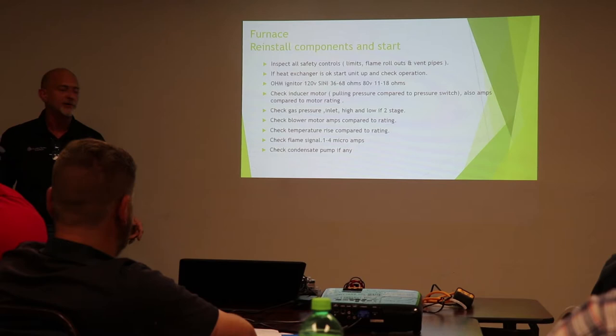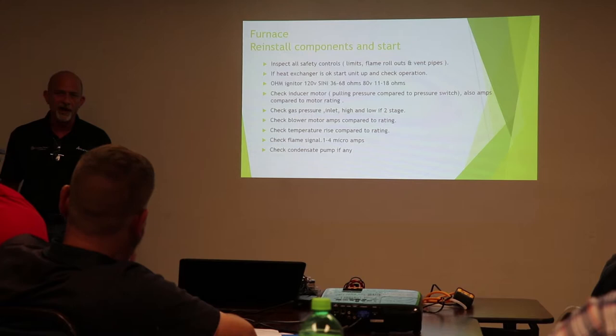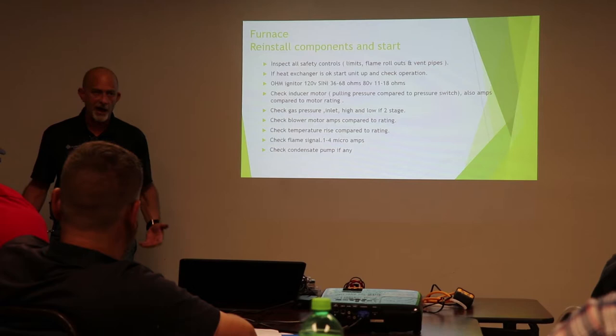Check your flame signal. Everybody checks the flame signal, right? Flame sensor. What about an old thermocouple? Do you guys check them? Do you clean a thermocouple? No? How much does a thermocouple cost? Average, $6. Are we going to go through the hassle of trying to clean a thermocouple? Some flame rods are more money. I can see possibly cleaning them.